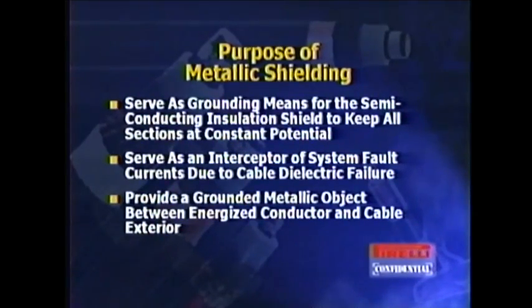In URD cables, typical utility applications, you would have a conductor that can also serve as an interceptor of system fault currents, whereas an industrial customer might have a separate ground to carry the fault currents to the ground. The utility customers generally combine this with the metallic shield, meaning that you'll have a heavy wire shield that serves as both an interceptor for fault currents and also a means of grounding that insulation shield.